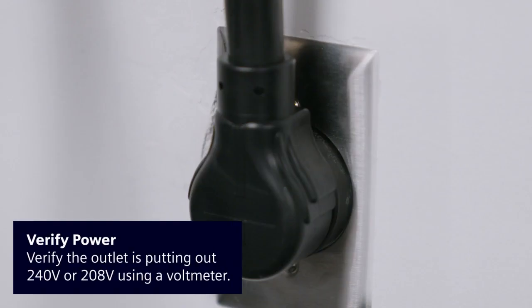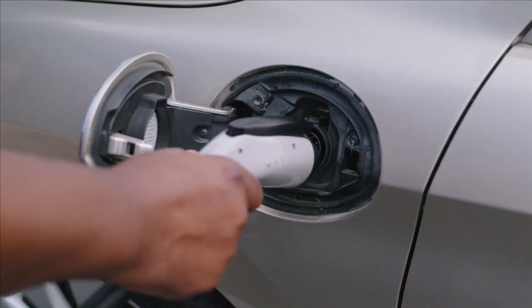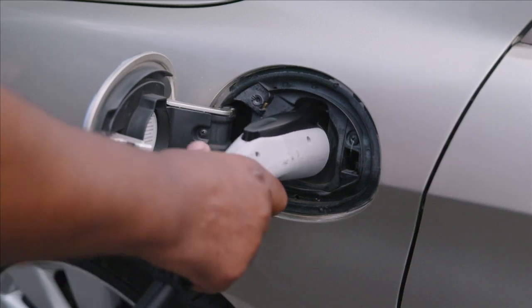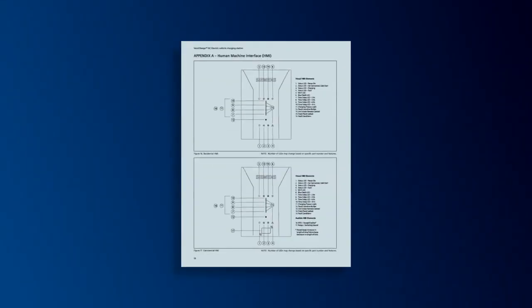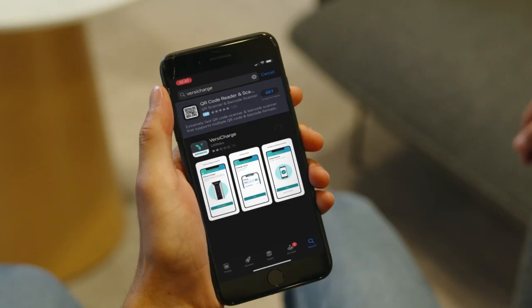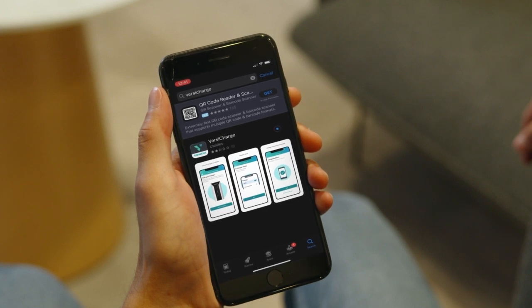If it does not, verify that the outlet or wire is putting out 240 or 208 volts using the voltmeter. With the power available light on, plug the electric vehicle supply equipment cable into the car. If you have any fault lights, please refer to the HMI figures in the manual. For residential home units, download the Siemens VersiCharge mobile app to get started using your charger. Find these applications at either Google Play or iOS stores.